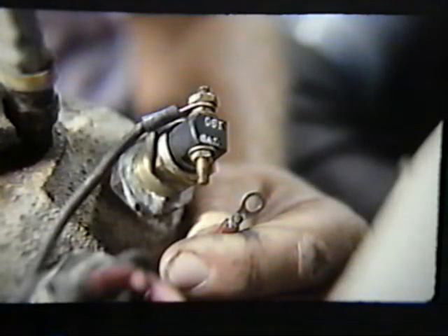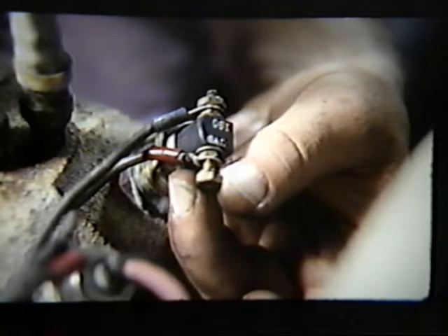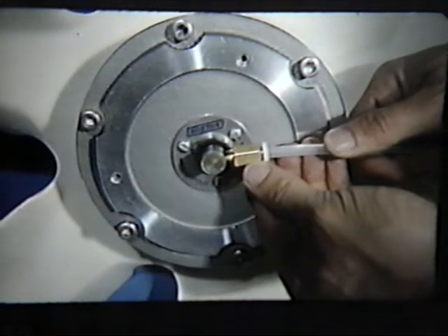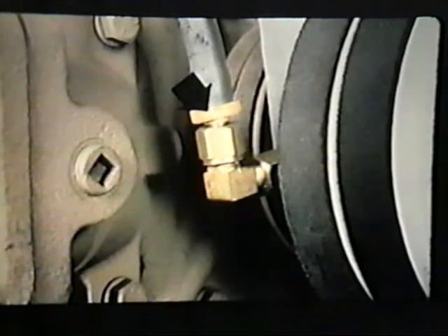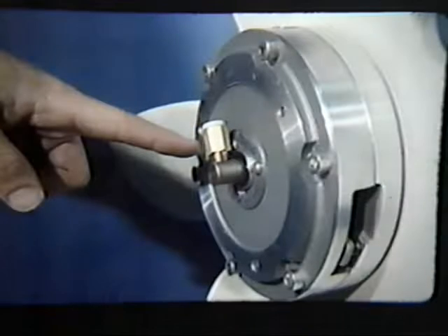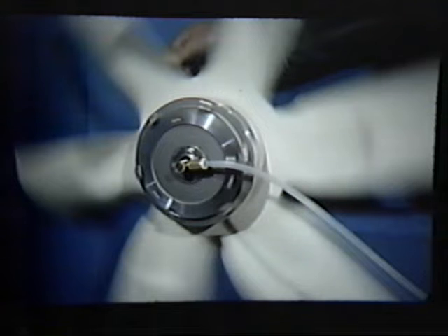By disconnecting the power source, the clutch will engage. To check the clutch for disengagement, reconnect the wire and the clutch will disengage. 3. Check air lines, fittings, and the rotary air union for air leaks and looseness. The rotary air union should be replaced as a unit if an air leak is detected. 4. Check bearings for rough spots or excessive drag by rotating the fan when the clutch is disengaged. The fan should rotate smoothly and evenly.